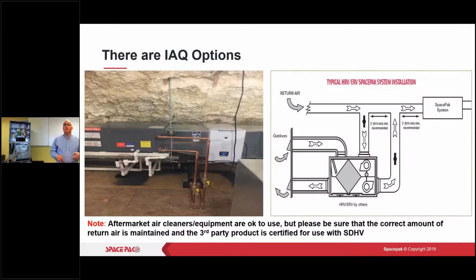You do have some indoor air quality options available where we can use an HRV or an ERV if that is needed for your job. It can be done. There's our typical configuration for that. But make sure we maintain the proper amount of return air. I know guys are going to thicker filters, everybody's worried about COVID and things like that, so we're trying to get down to the tiniest microns it can get. But we have to make sure we have enough return air in there.